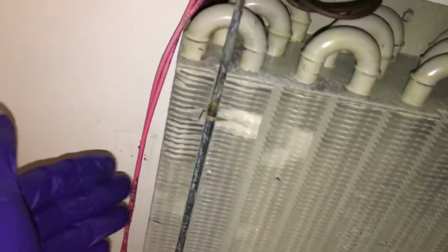And since I've never done one of these before, and I have to either replace or repair this evaporator, the leak of course has to be right on the back side of the fins from this plate right here, on the back side, somewhere right up inside the tubing right here. I haven't clearly identified exactly where it was, but it's somewhere back up in this area. I'll need to pull this evaporator down if I can't find it and fix it.